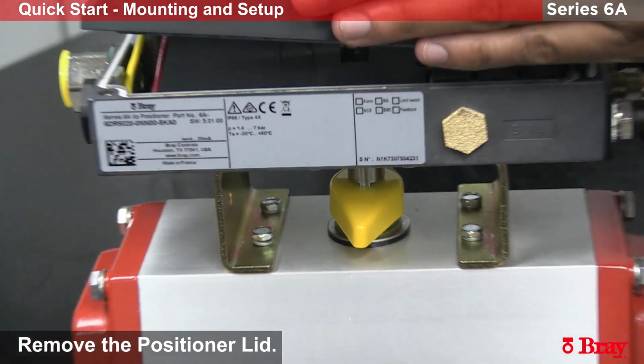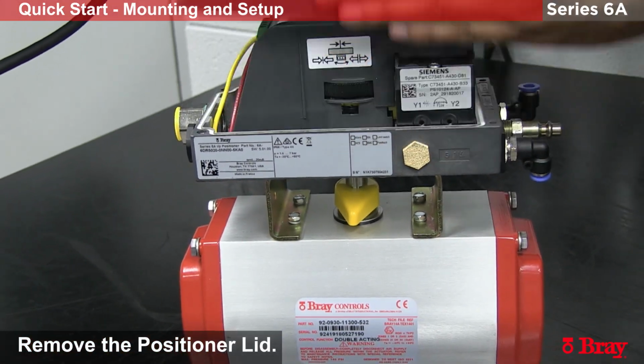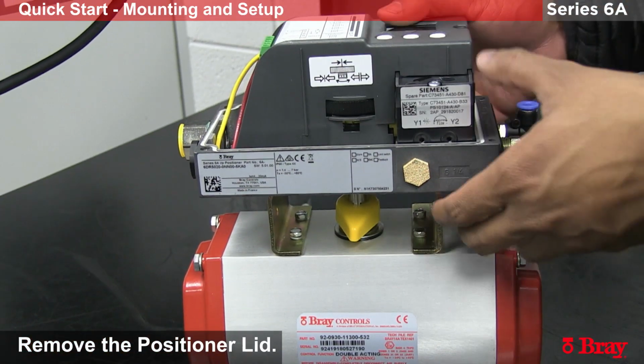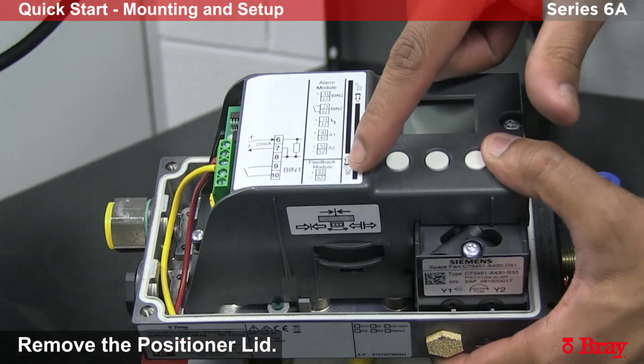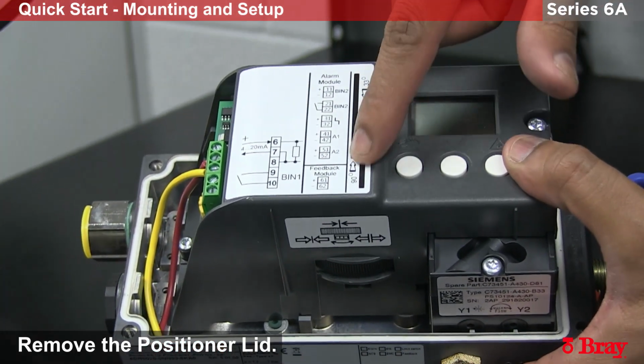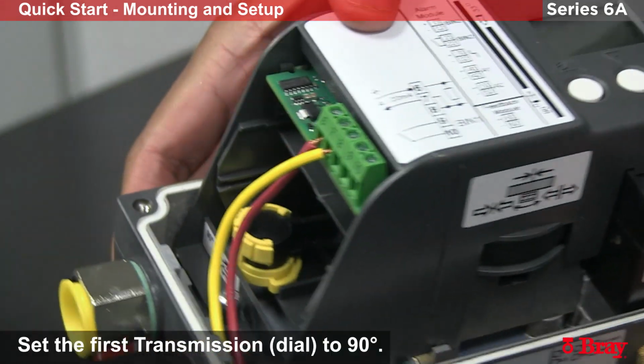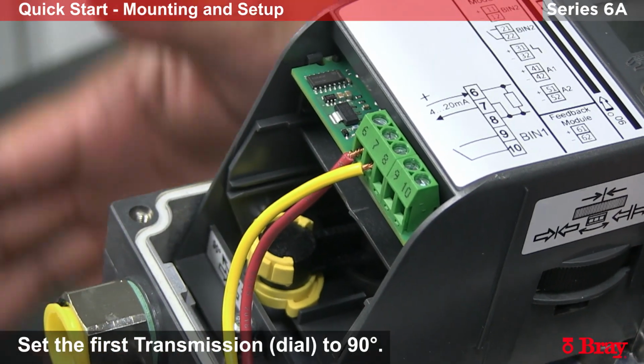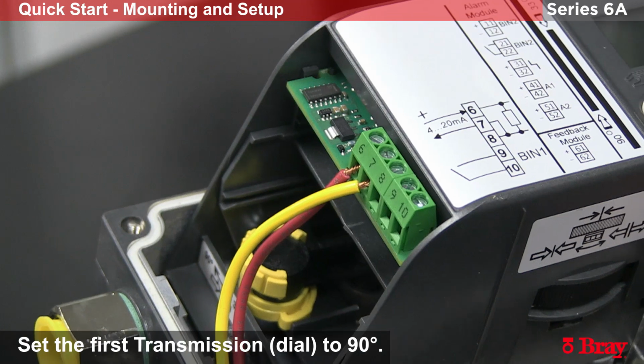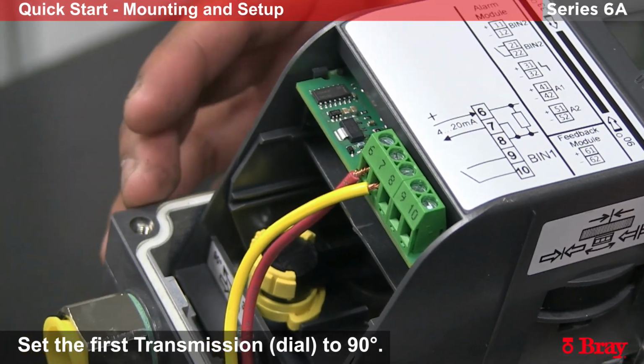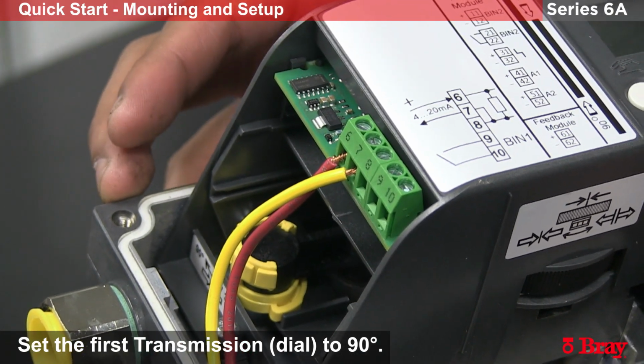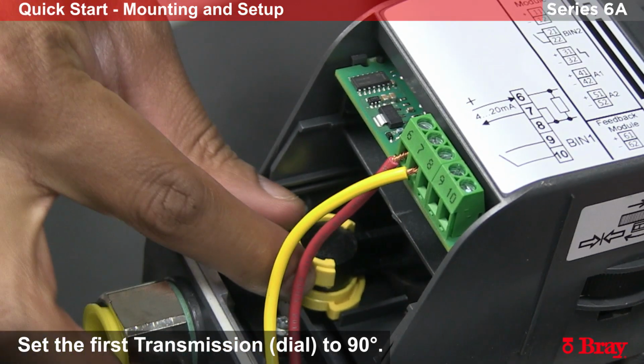To do this, we'll remove the lid, and what we need to do is set the position transmissions that are located here and here on the positioner. This being a rack and pinion actuator from Bray, it is a 90-degree actuator, so both transmissions will be set for 90 degrees of motion. This dial will need to be set to 90 degrees. There's 2 options, 33 degrees and 90 degrees. Make sure the arrow is pointing to the 90-degree option.